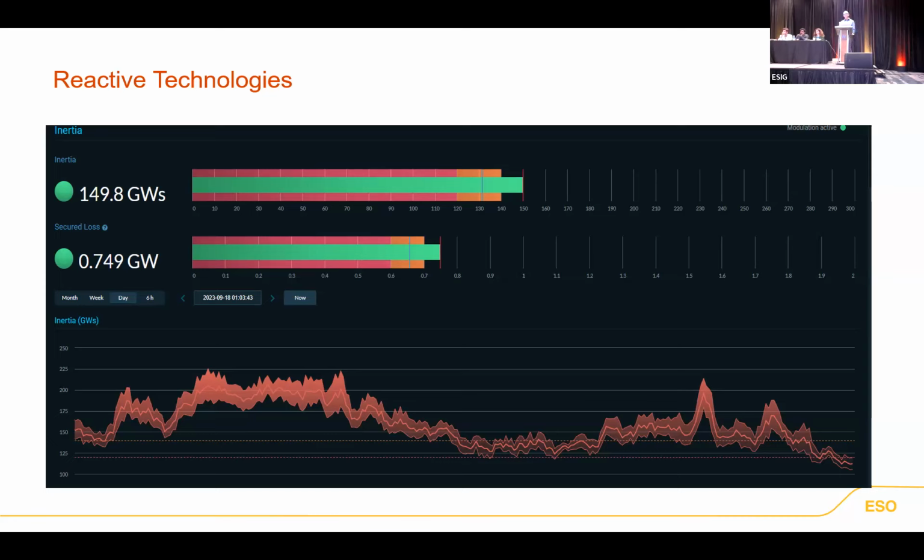And the beauty about the Reactive Technologies one is your 10 MVA injection into the system, at the lower inertia periods, is a bigger injection. Therefore, the size of the change in the MVA across the system is bigger, and therefore the measurement is even more accurate. So just at the time you really need a more accurate solution, that is the time the Reactive Technologies solution is giving a more accurate position.